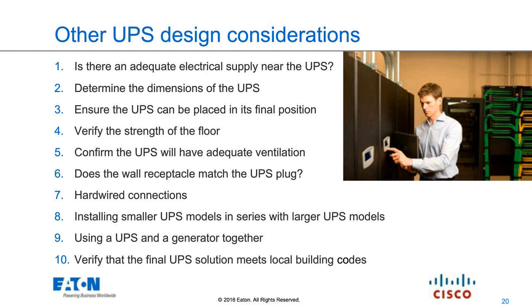We had a customer once that actually had to remove a wall because nobody thought about a 90-degree turn in a narrow hallway that was leading into the utility space where the UPS was going to be installed. So looking at all of that up front is absolutely critical. Floor strength. We have several larger systems that exceed the standard second floor or above limitation of about 100 pounds per square foot. Lead is very heavy, and the predominant chemistry of UPSs today is a valve-regulated lead-acid battery. That must be taken into consideration.